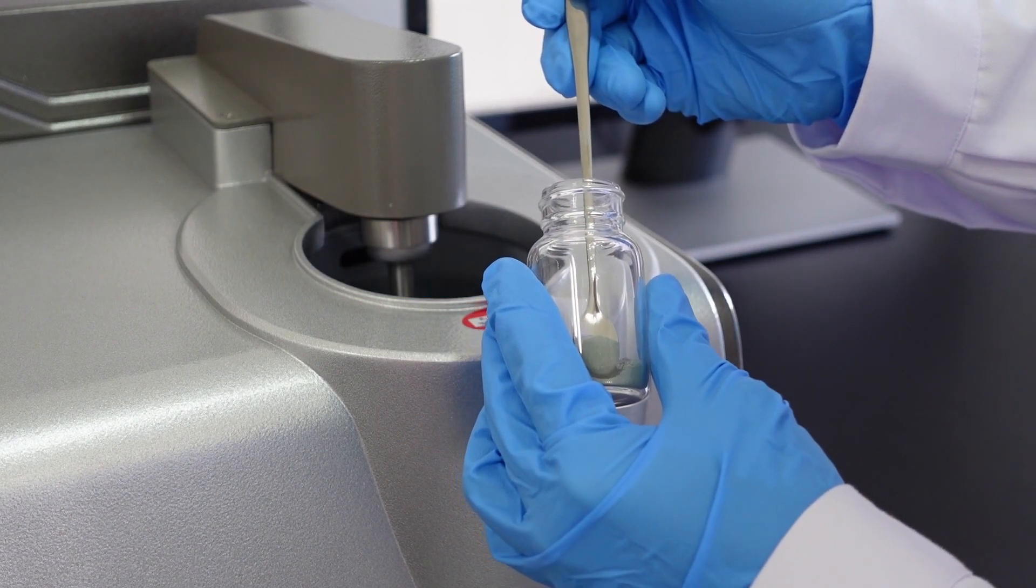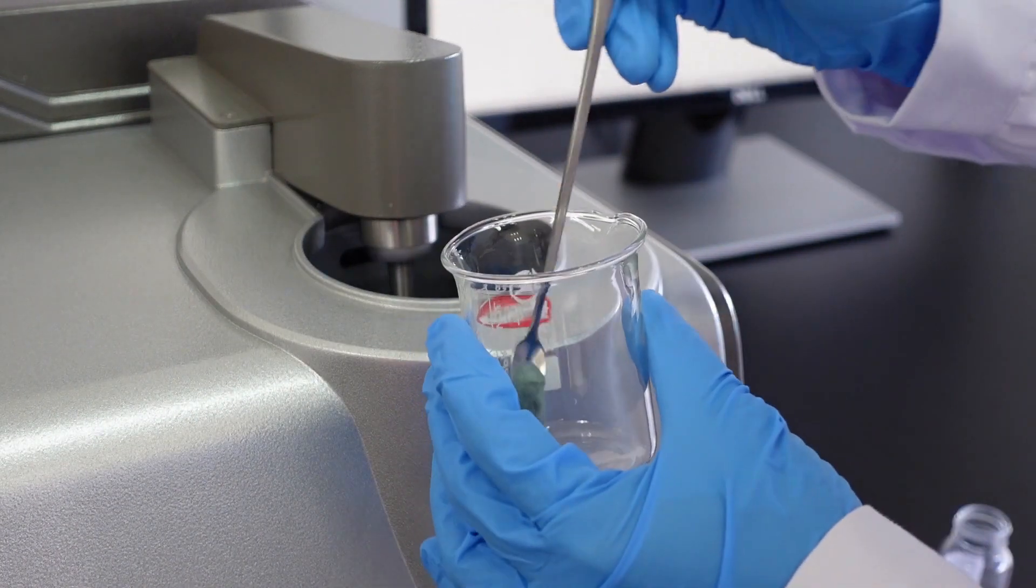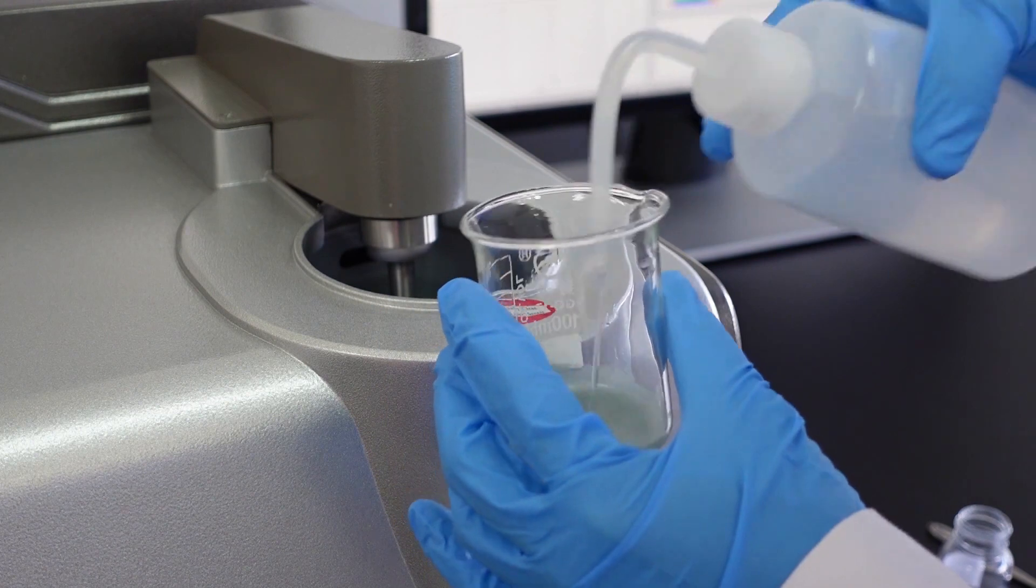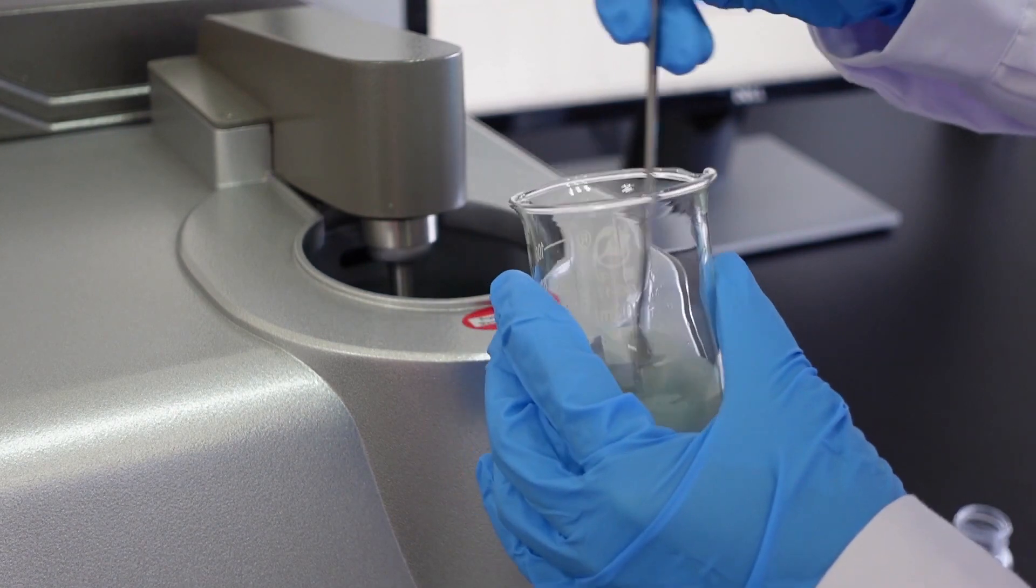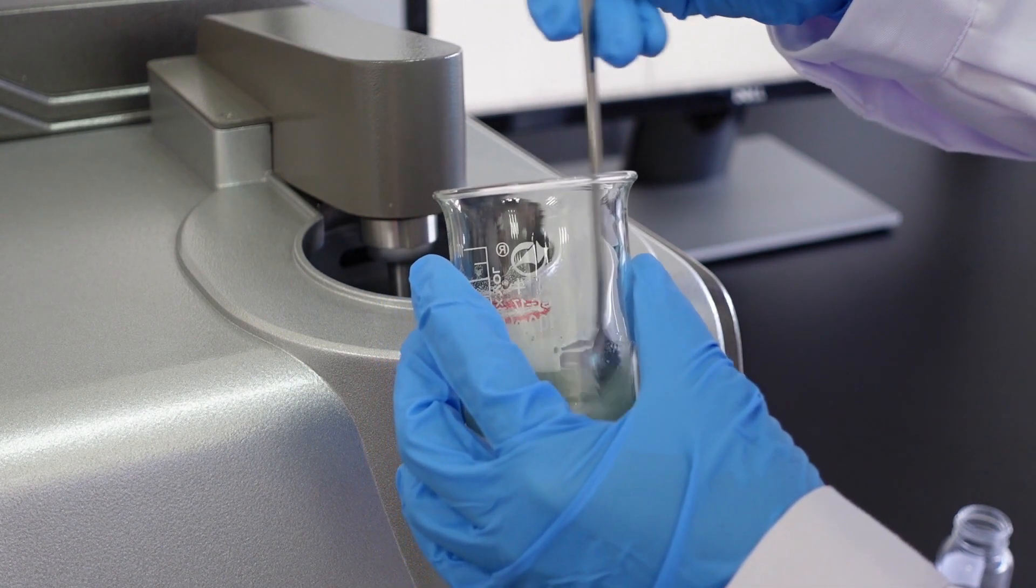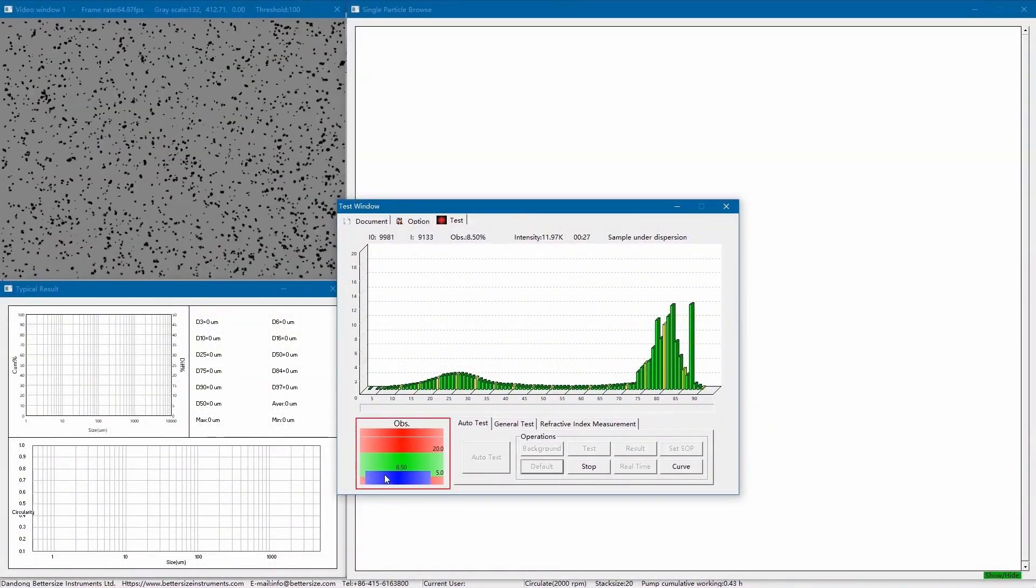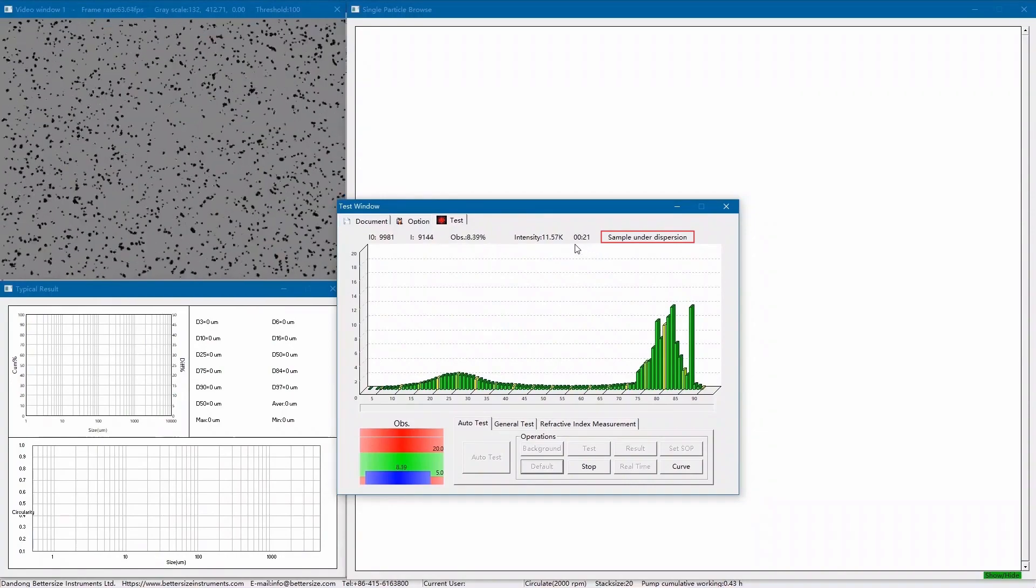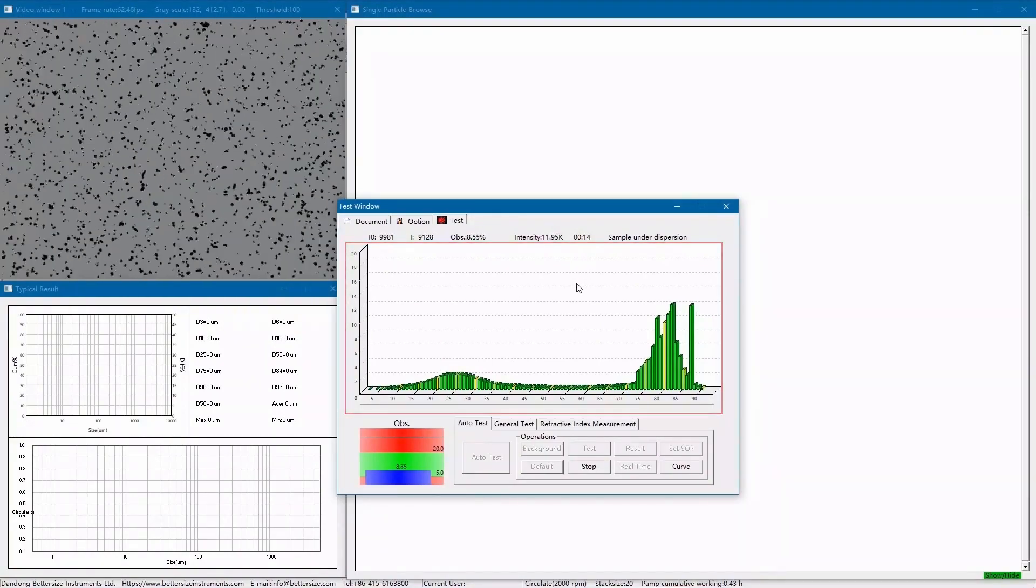A laser analyzer provides the particle size distribution of powders by measuring only a small fraction of samples. Therefore, the sample to be measured should be sufficiently representative, which is strongly related to the sampling method. Here, I use a small spoon to sample and pre-disperse it into the water in the beaker, and make sure that it is well dispersed in the water. Then I pour it directly into the circulation system, and please keep in mind to pour all the samples in the beaker without any part remaining. After the sample is added and the required circulation is reached, the instrument starts to disperse the sample. The previously set time is 30 seconds. After the dispersion is completed, the instrument will start the analysis automatically.